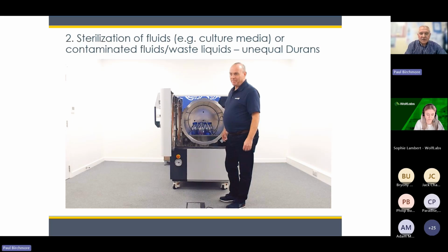You want consistency across your sterilization of your completed cycle, then use the same bottles. Don't have a mixture of sizes of bottles. Don't use mixtures of sizes of loads of liquid within the bottles, if you see what I mean. Be consistent and have a small quantity of one type of bottle with a type of liquid media inside it. You could reset the controller to have that cycle as a standard setting.